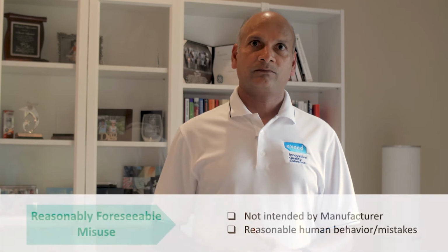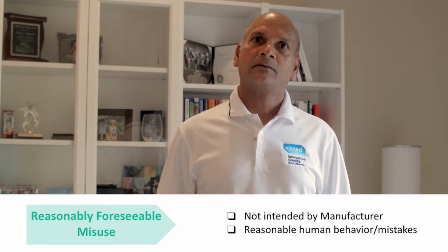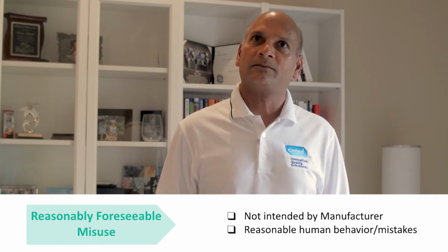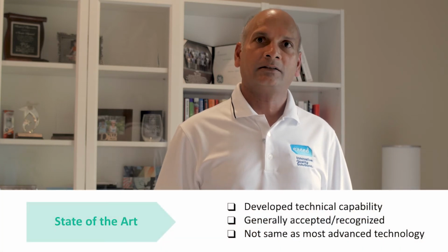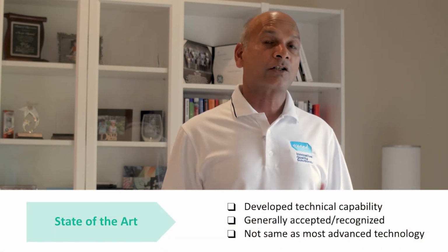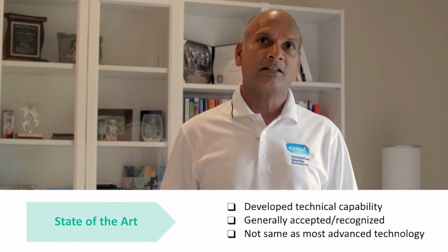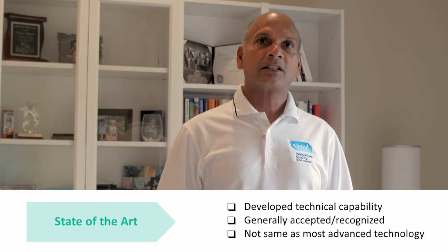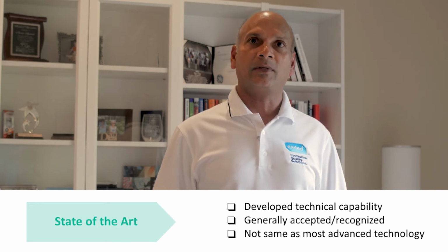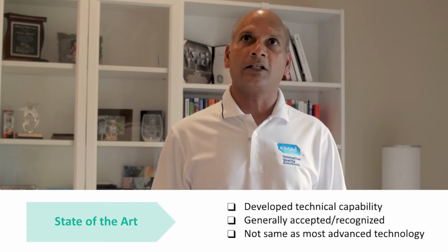The second term is reasonably foreseeable misuse, and these are unintended mistakes that can happen because of human behavior, but they are unintentional. The third term is state of the art, and this is best illustrated by an example. ISO 14971 is actually state of the art for risk management. State of the art is anything that's recognized by experts in a field as the state of knowledge or technical information. It doesn't have to be the most advanced technology. Why are these definitions important? Well, if you guessed that there are new requirements based on these definitions, then you are right.